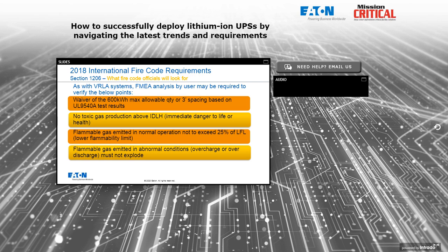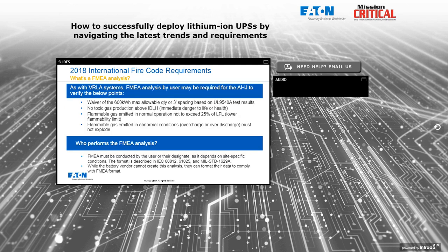What the fire code official is going to look for: an FMEA analysis by the user may be required to verify that the 600 kilowatt hour maximum allowable quantity and/or the three-foot spacing requirements can be waived based on FMEA and UL 9540A test results. They'll look at how much toxic gas would be produced under an emergency situation, making sure it remains below the IDLH — immediate danger to life or health — and that flammable gas does not exceed 25% of LFL. Gas emitted under overcharge or over-discharge conditions must not result in an explosion given the room volume and ventilation.